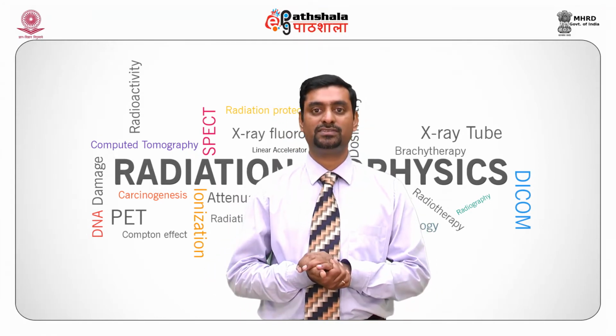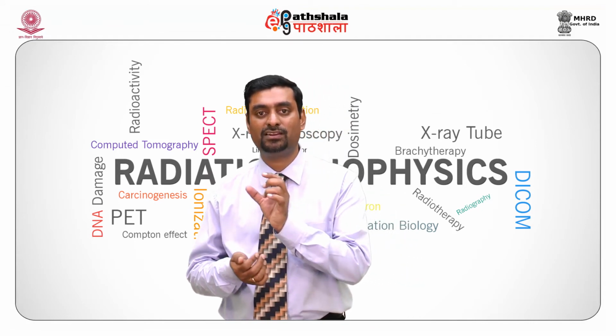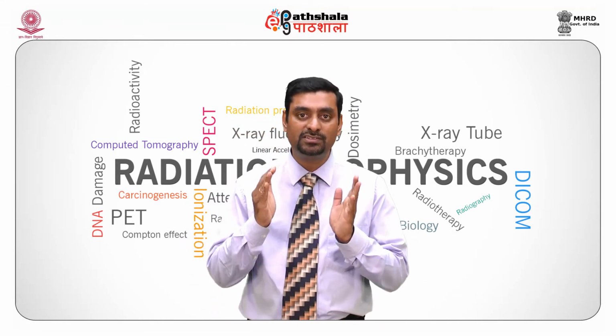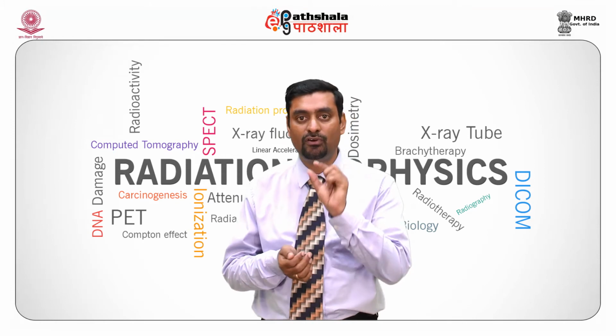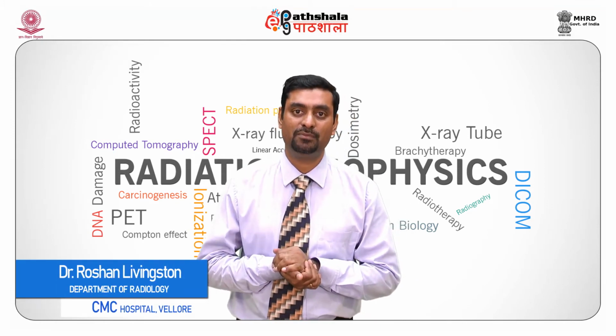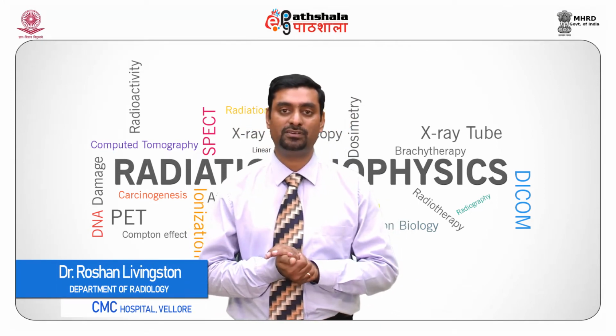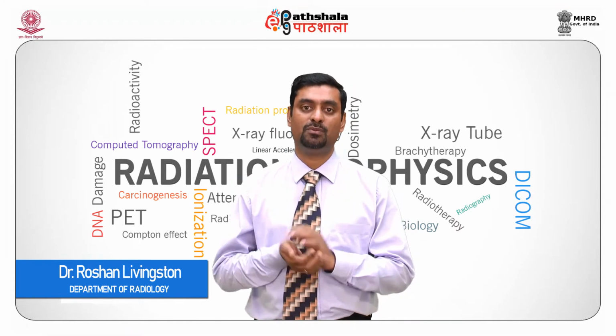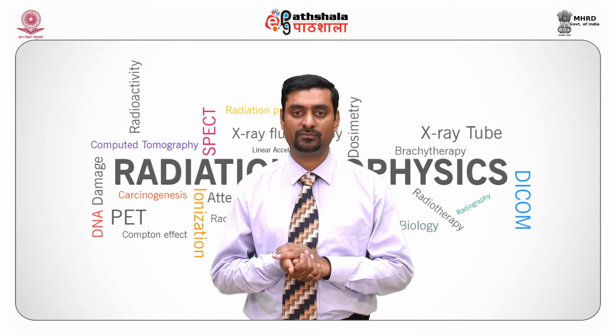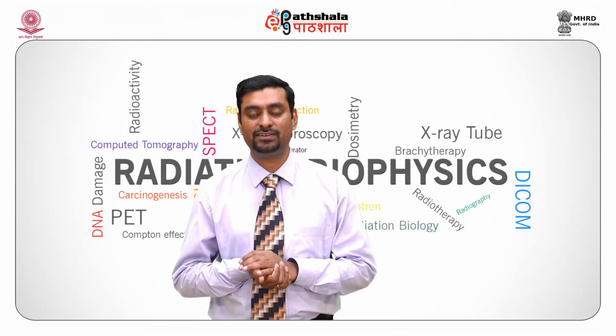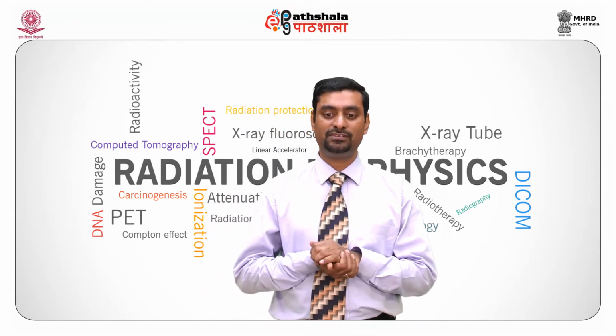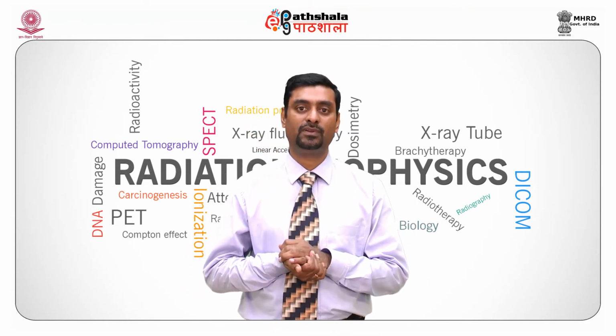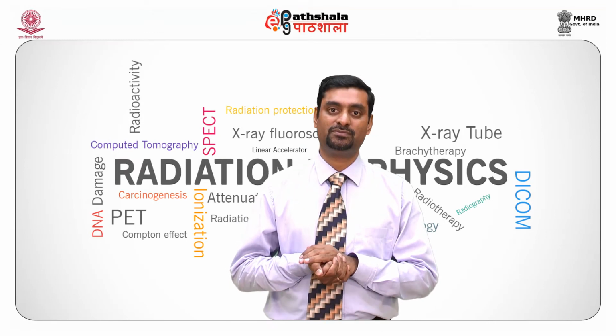However, the disadvantage is that it has an optical coupling, and the image may be demagnified to fall onto one CCD camera or an array of CCD cameras, where it may lose some of the image information. These are usually used for chest radiography, for dental imaging, orthopantomography, or in mammography systems these days.